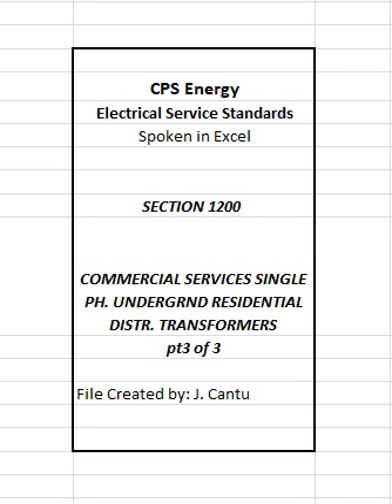Exception. Where the service is from an existing transformer, CPS Energy will designate a location where the customer will be responsible for furnishing and installing conduits, typically 5 feet from transformer or secondary enclosure. Customer shall coordinate with CPS Energy representative on the final conduit stub-ups at transformer. Note 1. Customer is not permitted to access energized CPS Energy equipment. Customer shall coordinate with CPS Energy for conduit and conductor installation. Note 2. The maximum lateral distance from transformer or secondary enclosure to metering location shall be 250 feet. Reference Article 705.